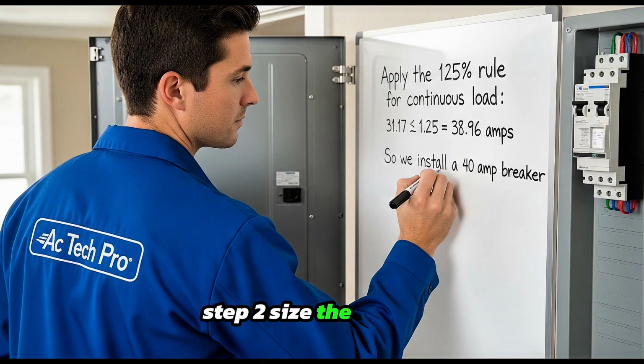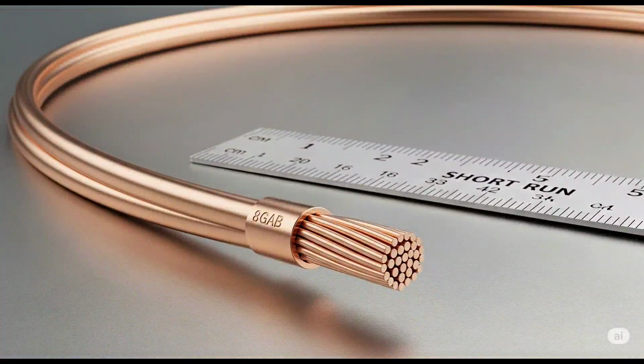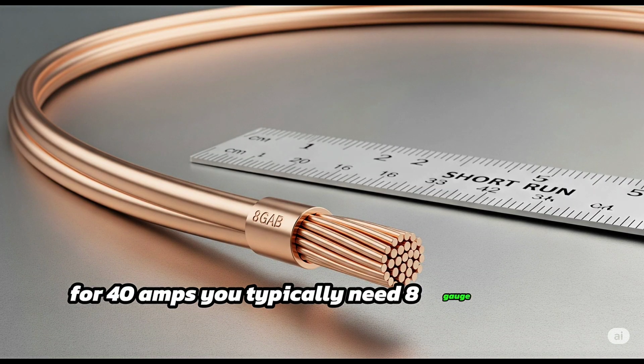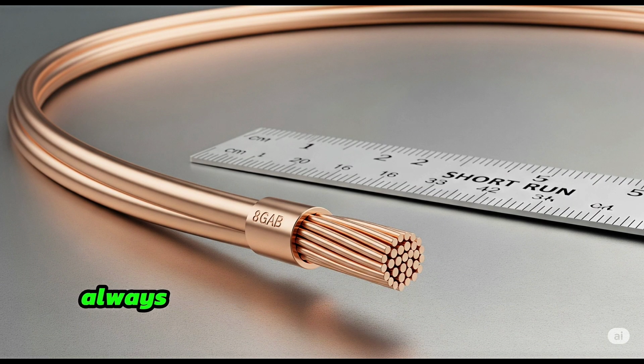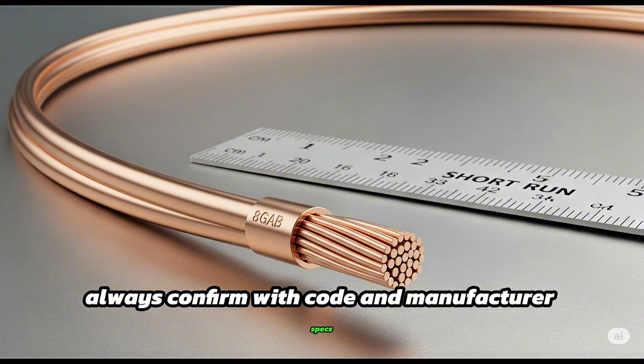Step 2. Size the breaker. Apply the 125% rule for continuous load. 31.17 times 1.25 is 38.96 amps. So we install a 40 amp breaker. Step 3. Wire size. For 40 amps, you typically need 8-gauge copper wire for short runs. Always confirm with code and manufacturer specs.